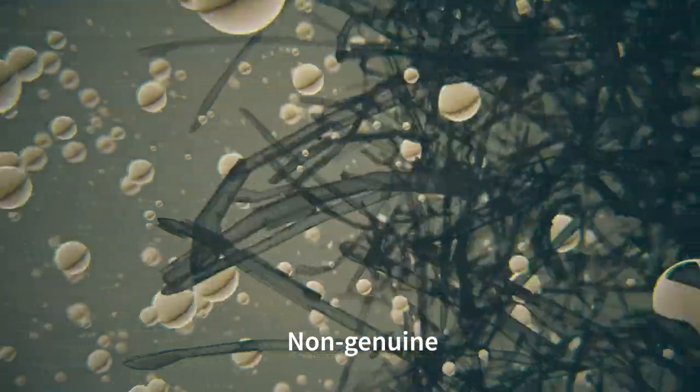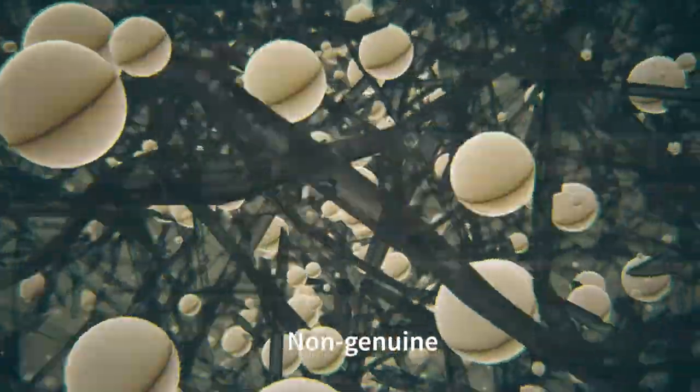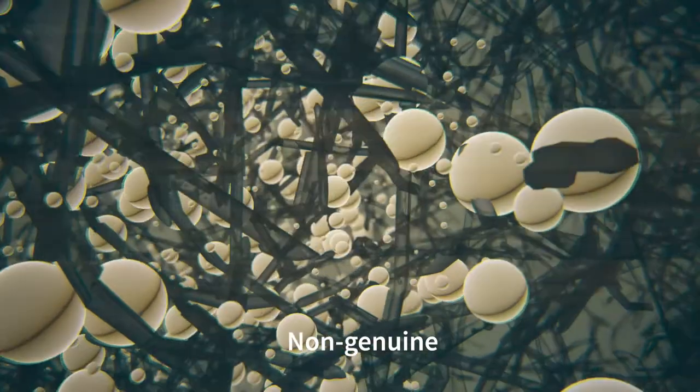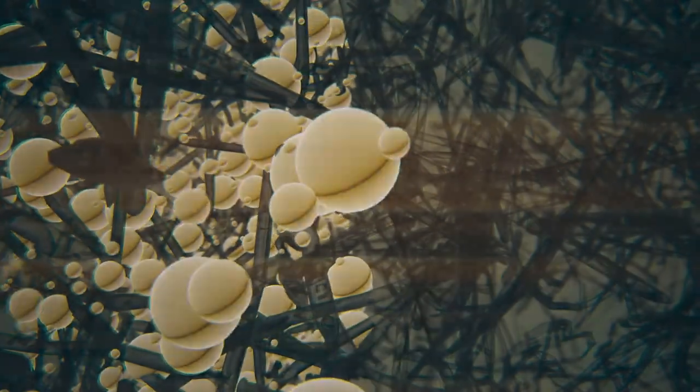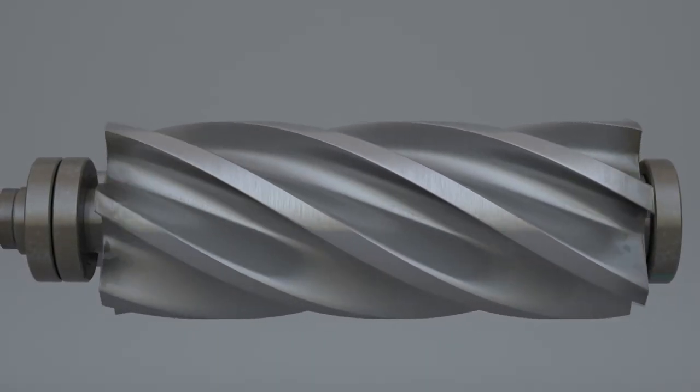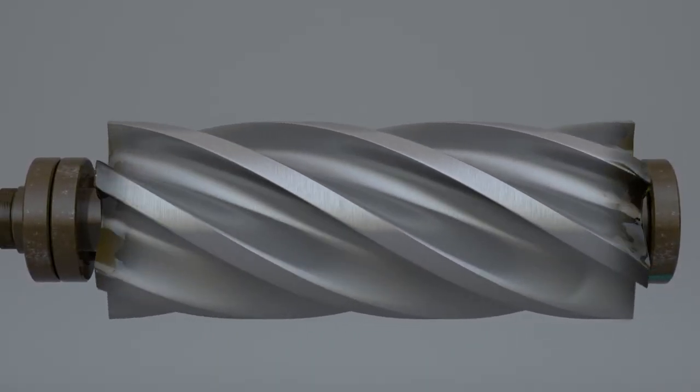Generic filters typically have a limited amount of low-quality cellulose paper. Premature saturation will cause high-pressure drops and a shortened filter lifetime. And unfiltered oil will be sent to the compressor element, leading to early element failure.